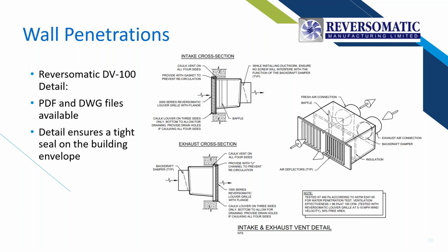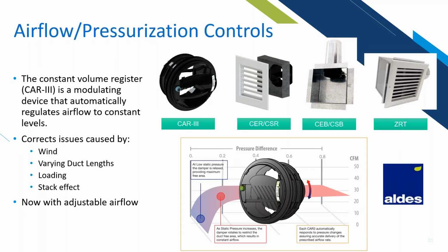So along those lines, you might not be doing a compartmentalized ventilation design, and you might be using a riser, and we still have a lot of great options for those types of designs as well. Our American Aldes constant airflow regulator, the CAR 3, is a modulating device that automatically regulates airflow to constant levels. And you can adjust it right in the face of it. So as long as you're delivering a constant pressure across that unit, you will get the airflow you've designed it for. We can use this device in a lot of different ways. We can put it in an exhaust register, in an exhaust boot or supply boot, and we can even put it in a zone register terminal that will help you modulate between airflow and shut off, or between minimum and maximum airflow.